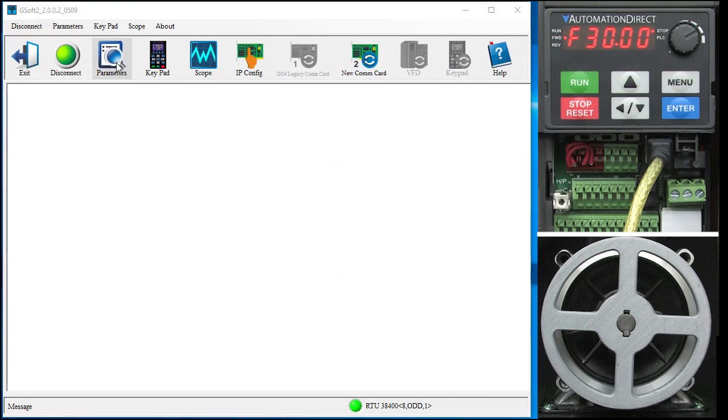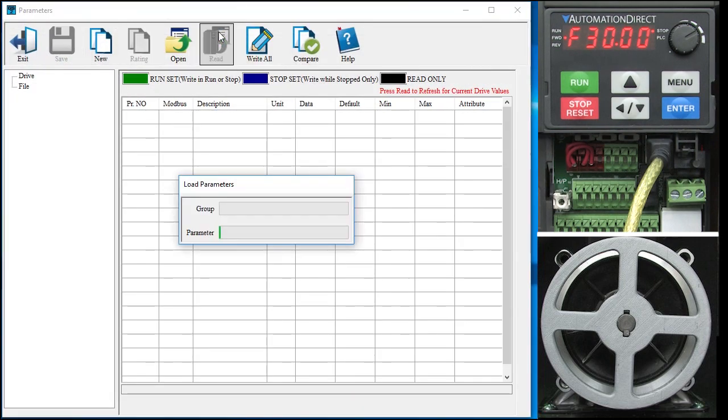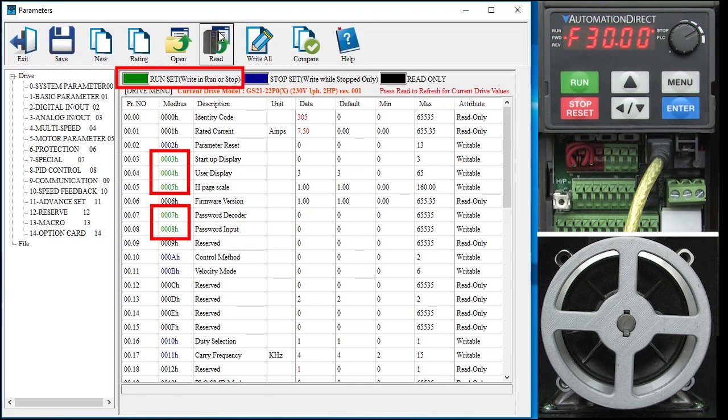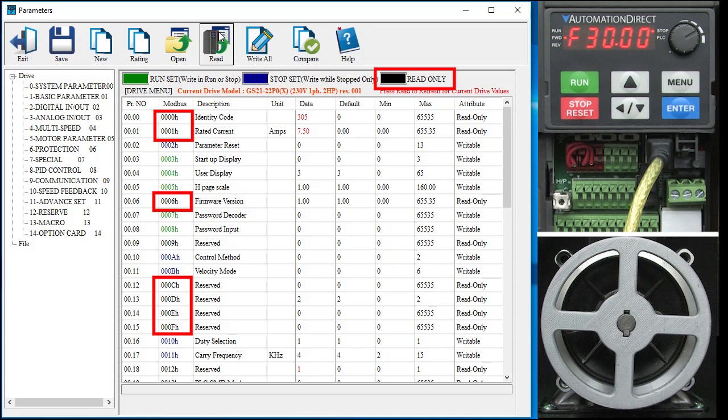Click on the parameters button and then click read to fetch all of the parameters from the drive. Green parameters can be written to while the motor is running. Blue parameters can only be written to when the motor is not running. And black parameters are read only parameters.